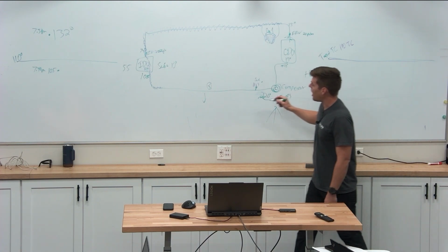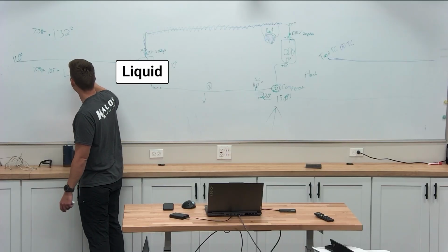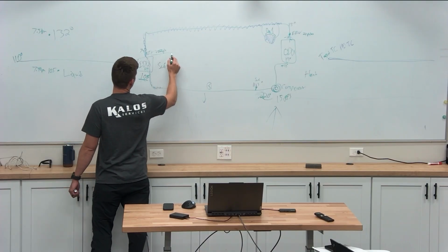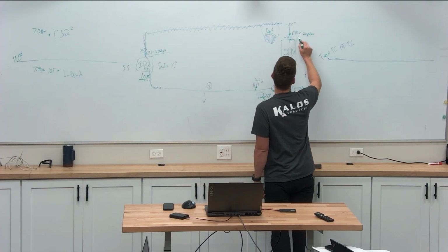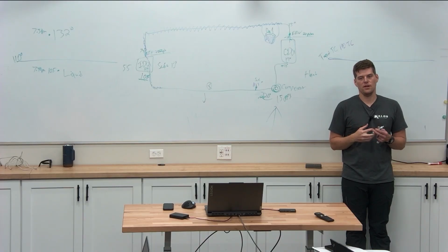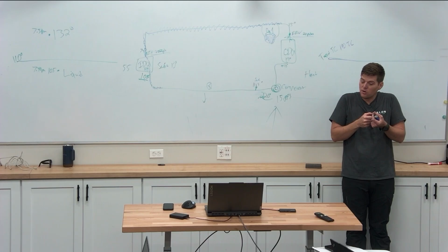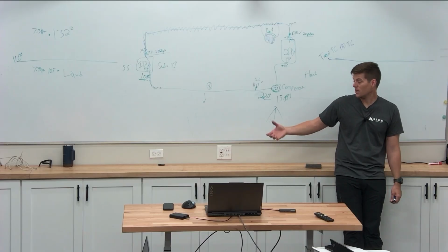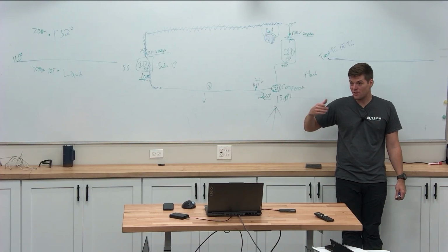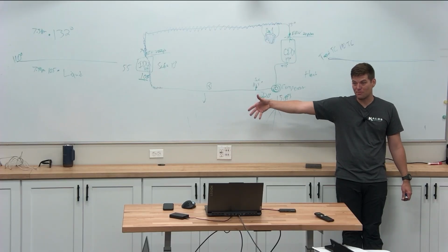We can see that I've got what on my hot gas line? I've got liquid. I know that I'm not metering refrigerant here, and I'm pinched all the way closed here. What do we know about pinched all the way closed? If I have a garden hose with a water nozzle on the end, and I turn the water on and just barely crack it open, it shoots out the end and peels the paint off my car. So I'm washing my car, because it's pollen season. Would you say that the pressure on that water hose is probably too high? Yes. I got a lot of water, a lot of pressure on the backside, right?